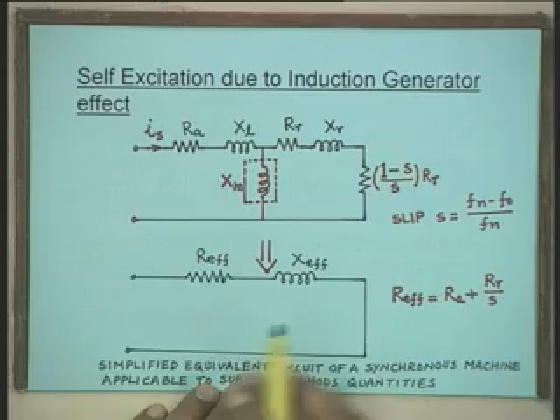Now, when you examine the self excitation due to induction generator effect, let us look at the equivalent circuit of the synchronous generator when it is behaving like an induction generator, right. We are not considering the synchronous generator aspect here, we are considering only that portion of the system which behaves like an induction generator. This is the armature resistance, this is the leakage reactance, this is the resistance of the rotor, this is the leakage reactance of the rotor, and this is the resistance which takes care of the loading, that is the load. Now, here this resistance R is (1 minus S) by S.